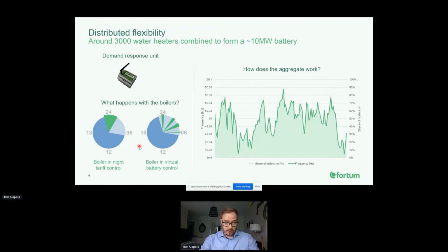This is an example of how it works. All of these boilers are on night tariff control. Typically, when the night tariff control turns on around 10 or 11 in the evening, the water boiler heats up for 2 to 3 to 4 hours, depending on how much hot water was used that day, then shuts off. But instead, we distribute the heating throughout the night, so each boiler gets the same amount of heating as in a typical case, but we heat the water when it's beneficial for the grid.